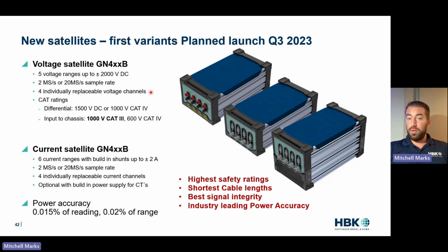The voltage channels are individually replaceable. If you have an accident, blow one out, nobody's going to get harmed. Swap that out. And they're also really, really good isolation. It's an incredible measurement from the differential standpoint. And we have all of the CAT ratings you can get. We have the 1500 volt DC rating. We have the 1000 volt Cat 3. It's really fantastic.